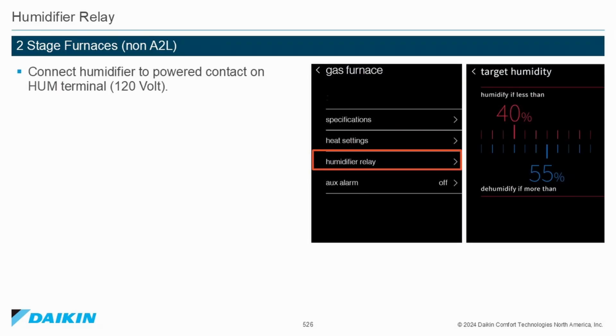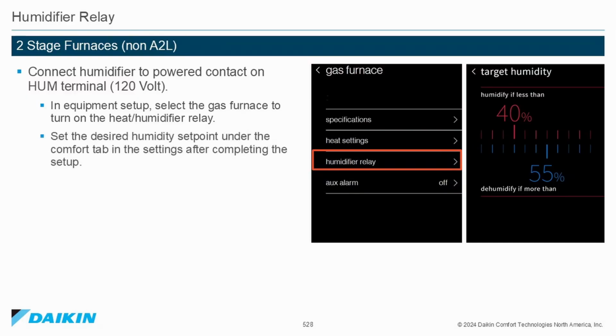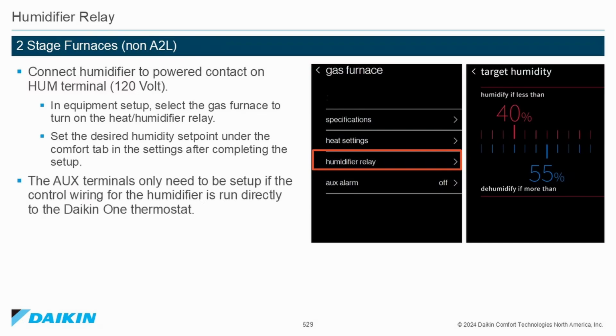Humidifier relay, 2-stage furnaces, non-A2L. Connect humidifier to the powered contact HUM terminal, 120-volt AC output. In equipment setup, select the gas furnace to turn on the heat humidifier relay. Set the desired humidity set point under the Comfort tab in the settings after completing the setup. The auxiliary terminals only need to be set up if the control wiring for the humidifier is run directly to the Daikin One thermostat.